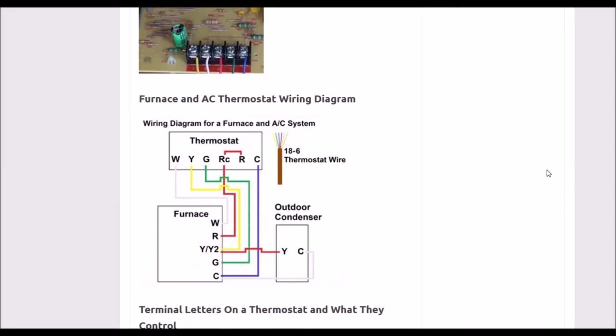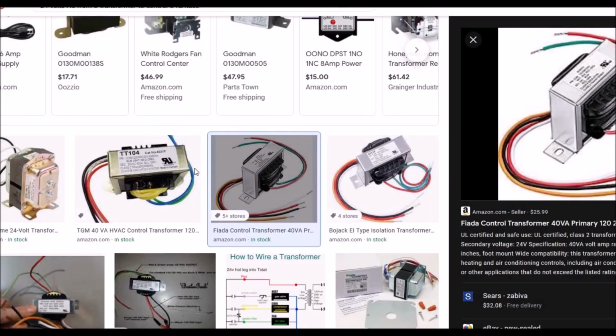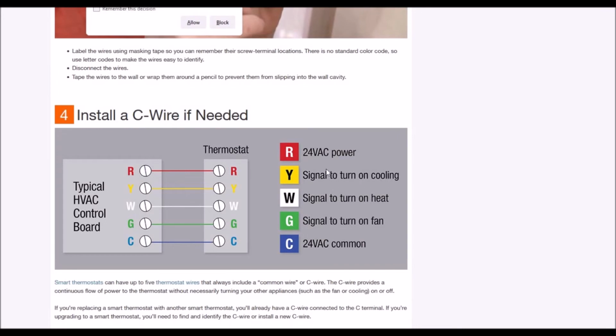So what can you do if your furnace is not working and you're trying to figure out if it's the thermostat wiring or if there's something wrong there? First of all, be sure you're getting 24 volts on this transformer. Find the transformer inside of your furnace or the location inside of your system, and just be sure on one side it's 120 and on the other side it's 24 volts. Then you can check if on R, on the thermostat, you're getting the 24 volts AC going through the transformer up to the thermostat. If you take your meter and you touch it on R and you touch it on C, that should be 24 volts, because the C is the common leg on the transformer and R is the hot wire on the transformer. So be sure you're getting voltage right there on these two wires. If you're not, then you have a problem with the transformer or in the wiring up to that point. That would be the first thing to check out.